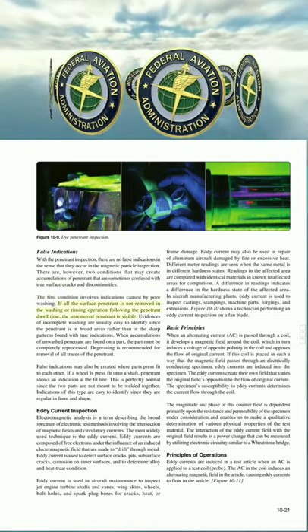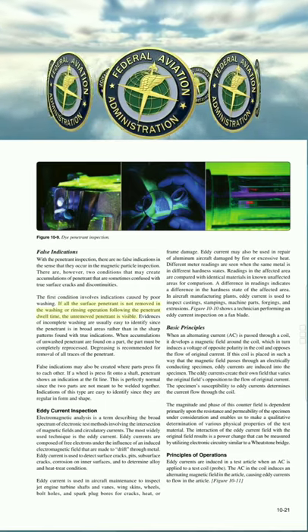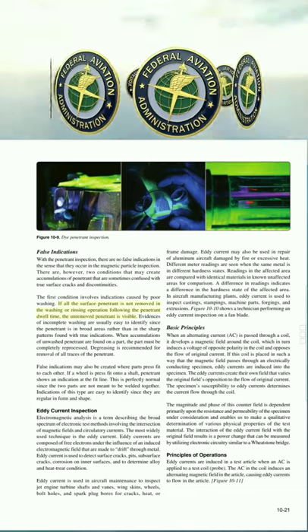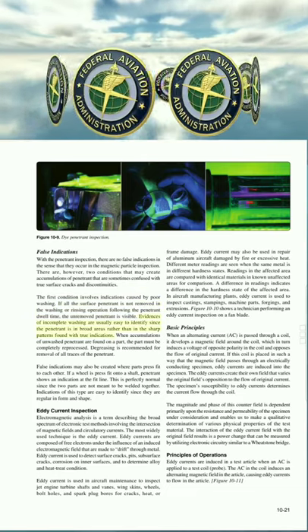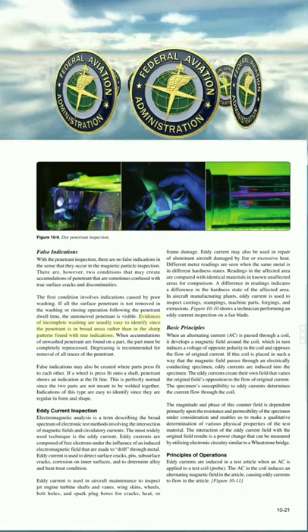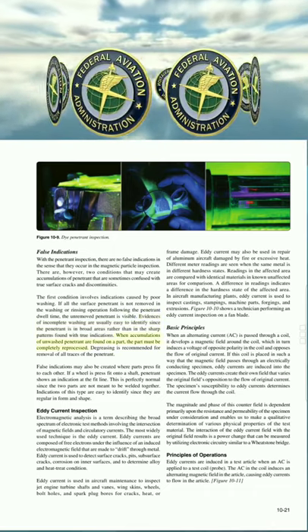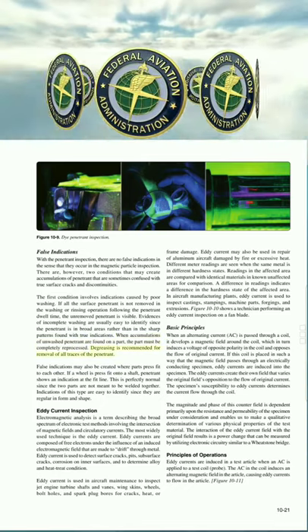If all the surface penetrant is not removed in the washing or rinsing operation following the penetrant dwell time, the unremoved penetrant is visible. Evidences of incomplete washing are usually easy to identify since the penetrant is in broad areas rather than in the sharp patterns found with true indications. When accumulations of unwashed penetrant are found on a part, the part must be completely reprocessed. Degreasing is recommended for removal of all traces of the penetrant.